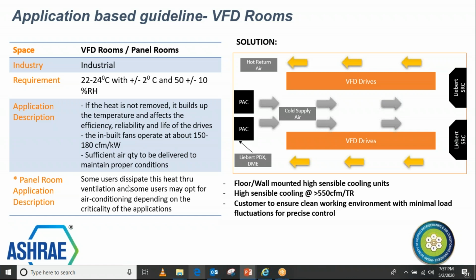In many applications people use ventilation for panel rooms, but we recommend a precision AC kind of system, because you can anyway achieve your ROI in less than a year, so it's a wise decision to go for these kinds of systems. And here you can have VFD panels and drives like this, with your cooling units placed on the opposite side or on one side based on the length of the drives, the dimensions, the load of the room, and the overall layout. You can have various different types of cooling units.